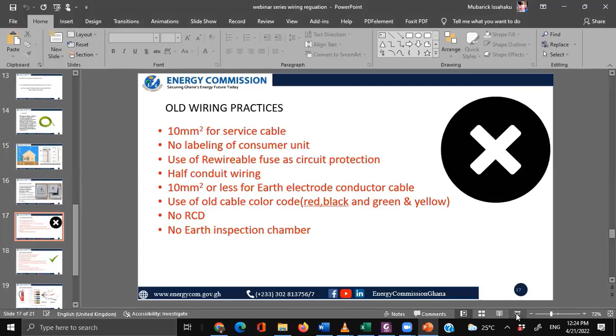Then half conduit wiring. We'll pull up a picture very soon, then you would appreciate what half conduit wiring is. Those who are privy to an electrician working on their facility realize that after the electrician has chiseled the wall or used a cutter on the wall, they place a PVC pipe in it. Those PVC pipes are supposed to house your cables. They're not supposed to run bare in the wall or on the ceiling. So an electrician will do the wiring and the PVC pipe would run in the wall, okay. But when it gets to the ceiling, where the wooden structure is, he leaves it bare to run on it. It's against our standard. It's not supposed to be done.